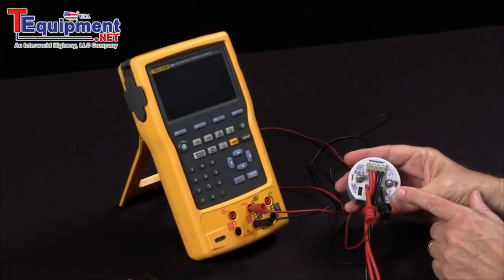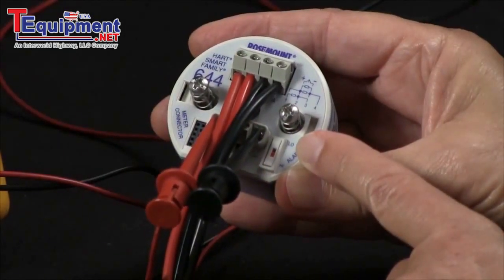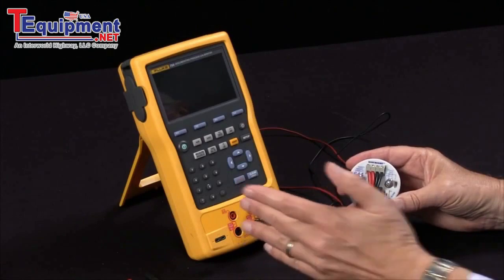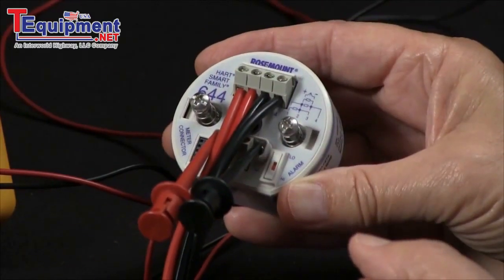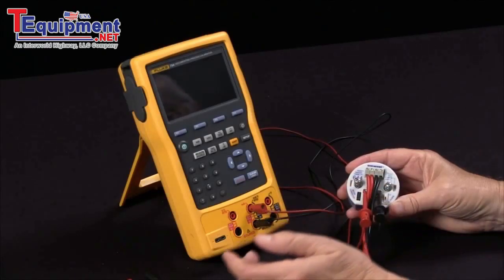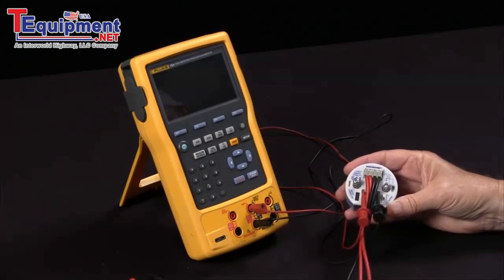We have a 4-wire platinum 100 ohm RTD transmitter that we're going to be using today, and we're going to use the Fluke 754 documenting process calibrator to source RTD to this transmitter and let it measure it. You'll notice that it's configured as a 4-wire device, so we bring the four wires out and jump them together at the end with stackable connectors.